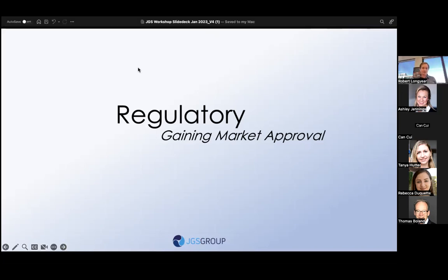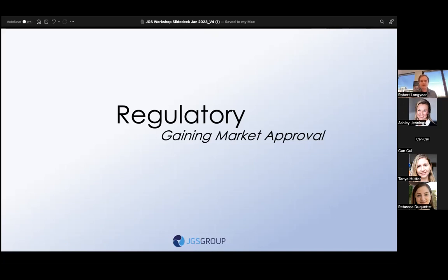So the FDA approves things based on the indication. So there's a world where you're going after approval with the technology, and I assume by specialty you mean a medical specialty. So if nephrologists are using the technology for something, but you're a cardiologist and you want to use it now for a different purpose, a different indication, then you'll have to go through a separate classification through the FDA. It could be the same technology, and you'll say, hey, this other use case and submission for nephrology is using the same technology. That's my technology predicate, but my actual use case and indication for use is this separate filing here.